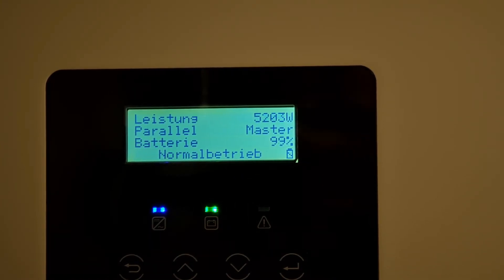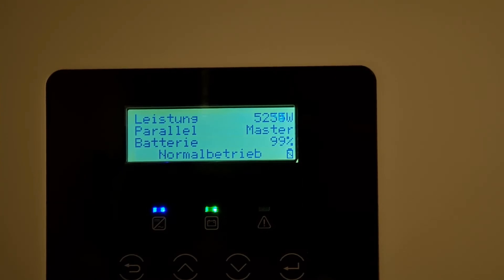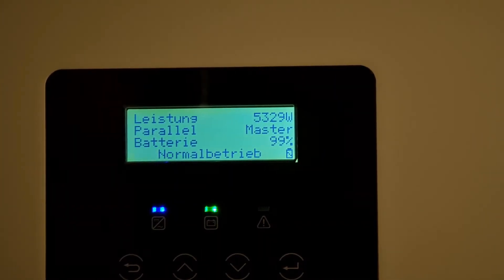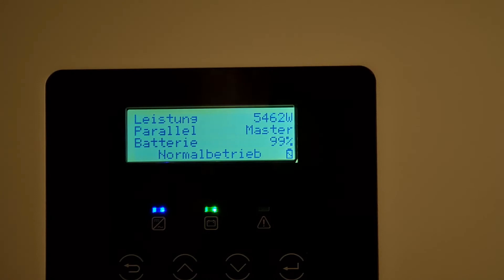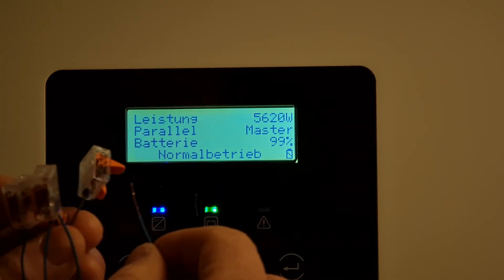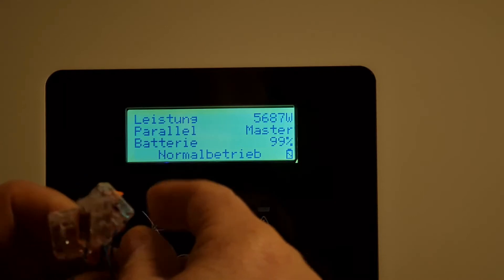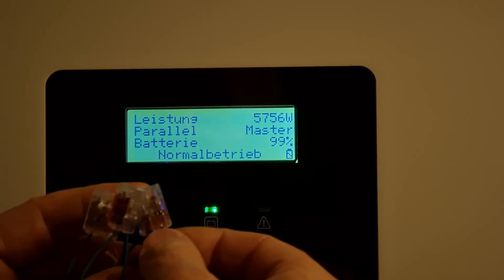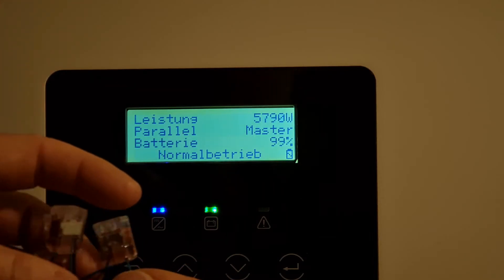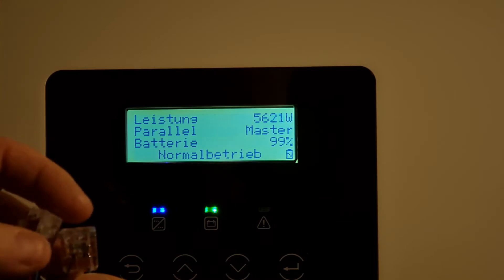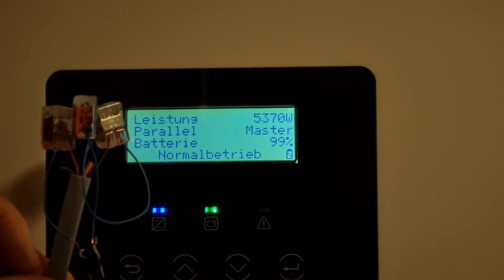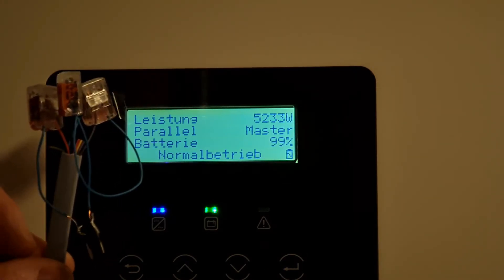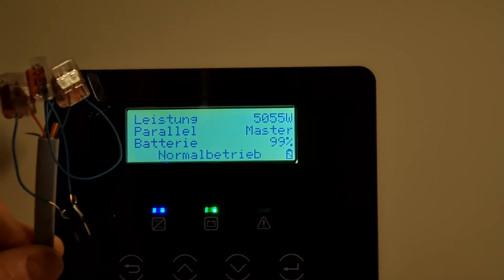The inverter will no longer ramp up as it's doing right now, but instead will ramp back down to zero. This is the primary cable connection and this is the second additional connection. When the grid operator closes their potential-free contact, the following happens. That component should now be securely in place. It takes a little while — the whole thing is a bit sluggish — but you can see it's no longer ramping up; instead it's ramping down and will keep doing that until it shows zero.